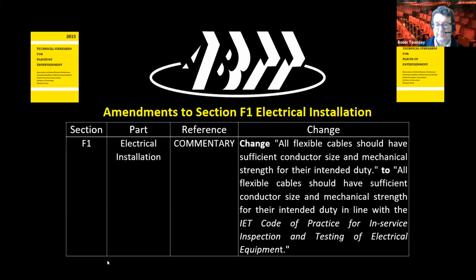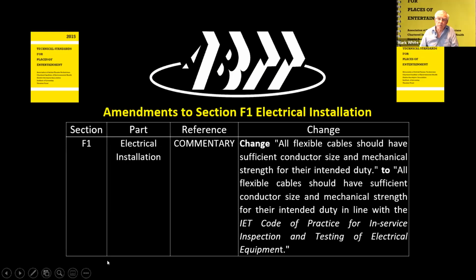Certainly. Now, this is to do with flexible cables. This comes up an enormous amount very often. And basically, we say that in this case, every flexible extension cable on a stage should have a minimum cross-sectional area of 2.5 millimeters squared. So we're simply saying that for various reasons, 1.5 millimeters squared 3-core cable is not enough, and 1 millimeter is definitely not enough. It's to do with maintaining something called earth loop impedances, particularly over the sort of lengths of cable that we typically find on stages.